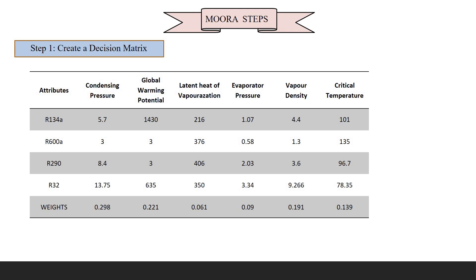Step 1 is to create the decision matrix using four alternatives — R134A, R600A, R290, and R32 — and six attributes: condensing pressure, global warming potential, latent heat of vaporization, evaporator pressure, vapor density, and critical temperature.